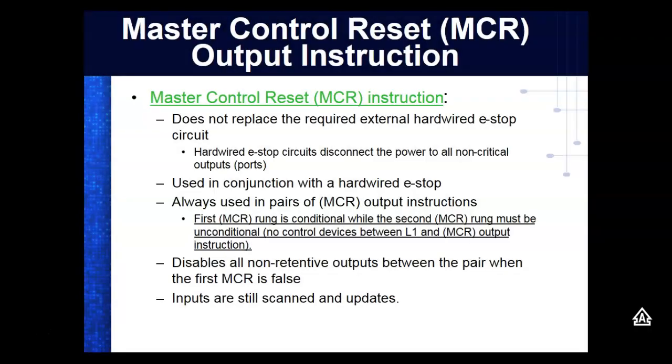Master control reset instruction. This is also available in RSLogix 500. Does not replace the required external hardware e-stop circuit. So your e-stop circuit should be hardwired. Why is that? Has your phone ever locked up on you? Has anybody ever reset their phone?